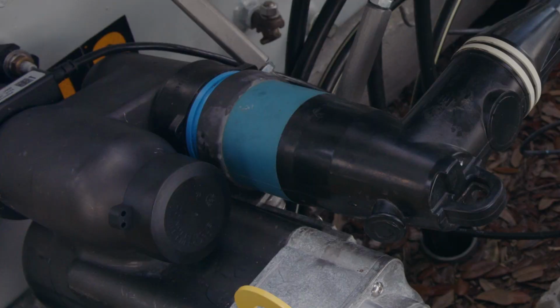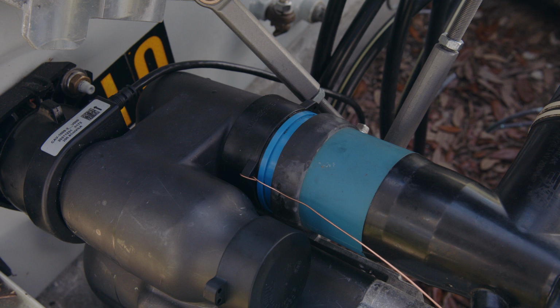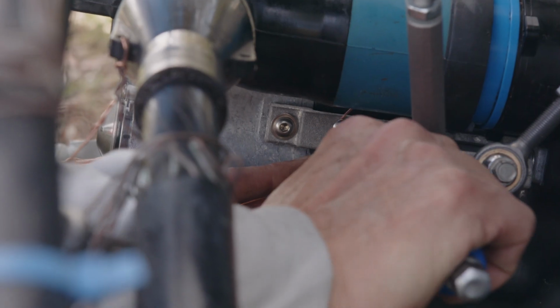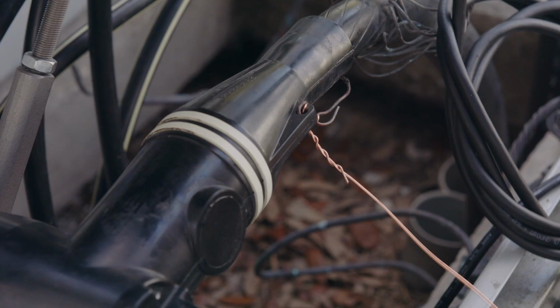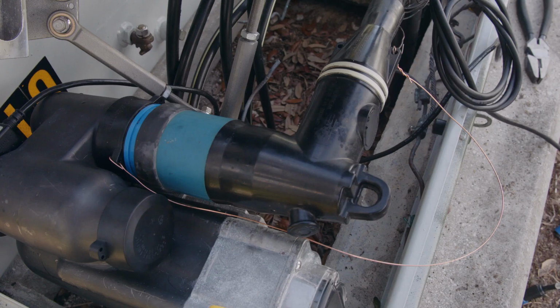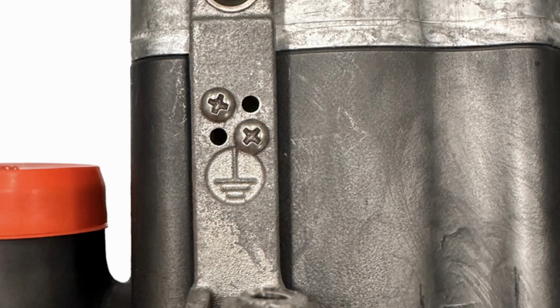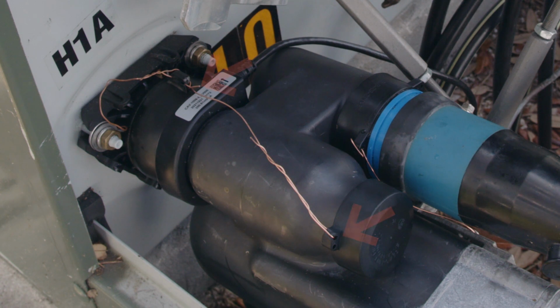Step 1. Install the load break insert and connecting cable according to standard utility practice. Step 2. Connect the drain wire from the tab on the load break insert to the grounding point on the bushing well interrupter and continue on to the elbow neutral. Leave enough slack in the drain wire to enable parking if desired. The grounding point is marked with the symbol for earth ground and 2 holes are provided for attaching drain wires. Be sure to ground the H1A bushing well interrupter cap as shown here.